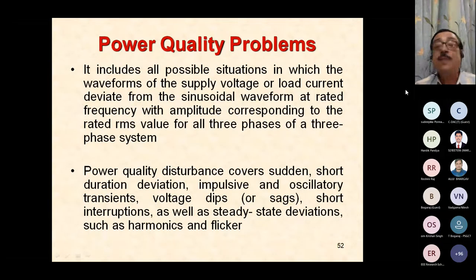So power quality problem includes all possible situations in which the waveform of the supply voltage or load current deviates from the sinusoidal waveform at rated frequency with amplitude corresponding to the rated RMS value for all three phases of a three-phase system. You're talking about a balanced system literally here. And power quality disturbances cover sudden, short duration deviations, impulsive and oscillatory transients, voltage dips or sags, short interruptions, as well as steady state deviations such as harmonics and flickers. Everything is a power quality problem.